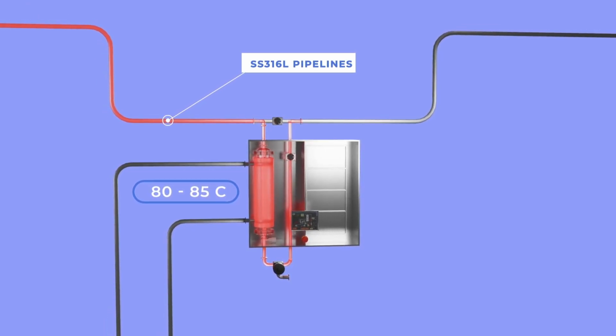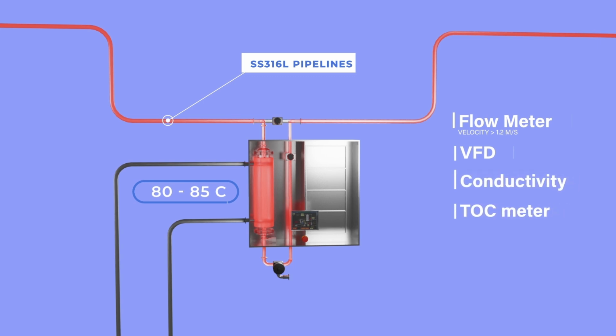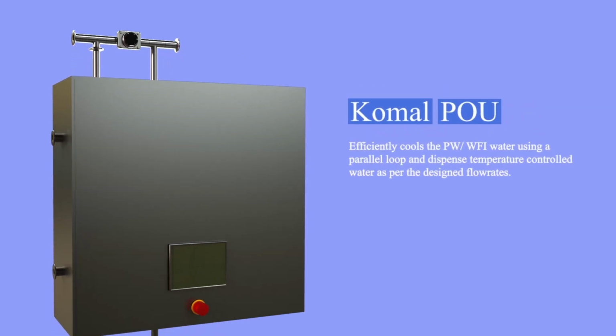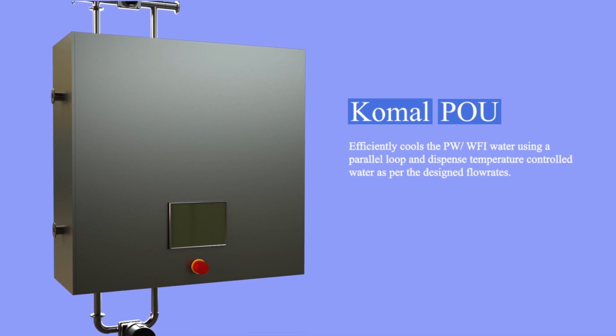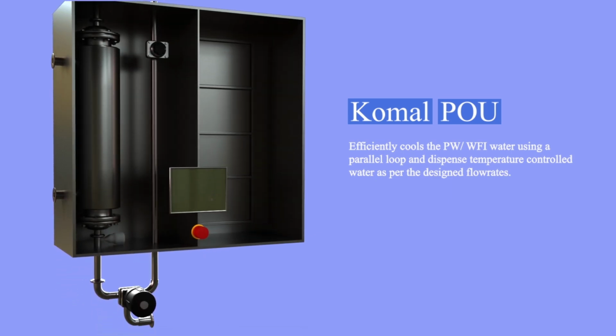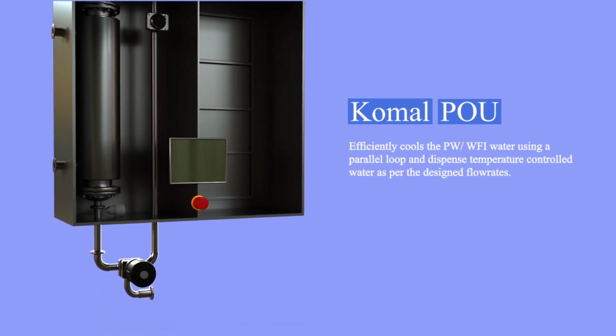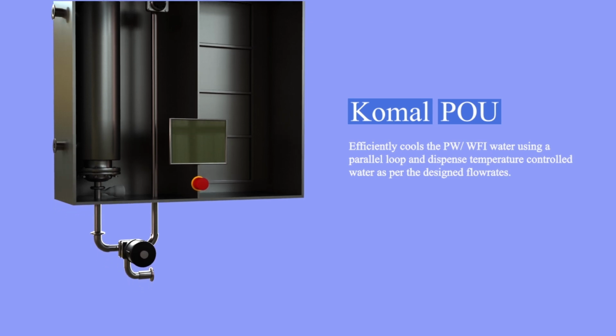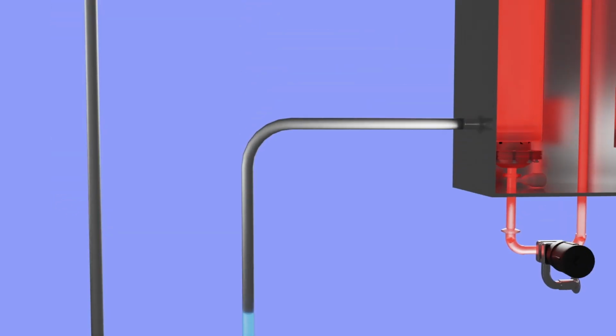heat exchanger. The distribution loop return has instruments like a flowmeter to maintain velocity greater than 1.2 meters per second using a VFD, and conductivity, temperature and a TOC meter to make sure that the water quality is maintained. However, the point of use requires the water at room temperature, and hence we require a localized heat exchanger. Komal point of use heat exchanger employs the latest technology to efficiently cool the POU water using a parallel loop.